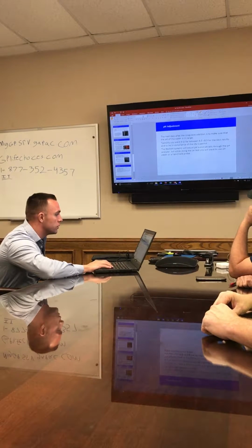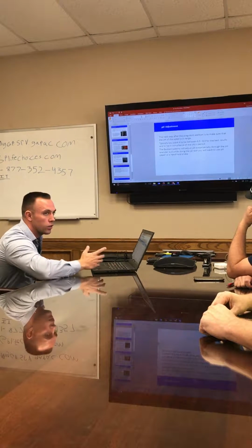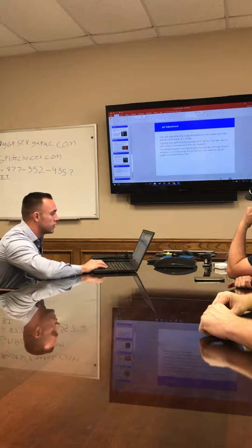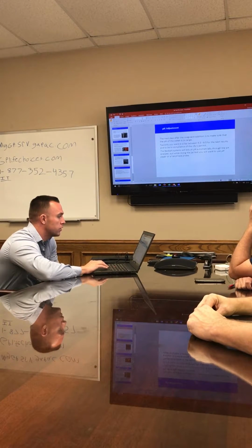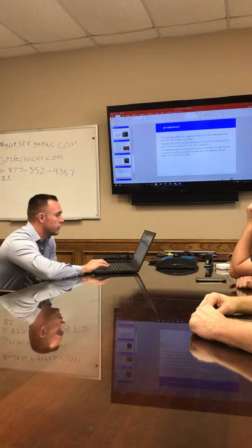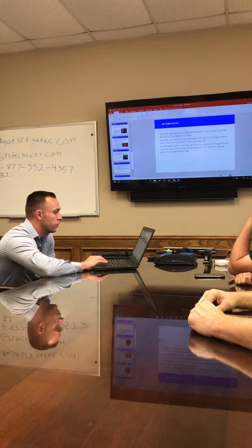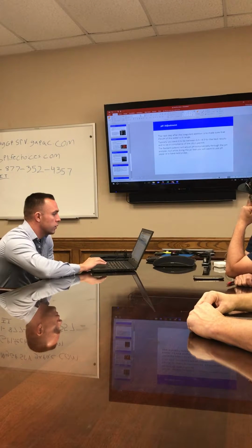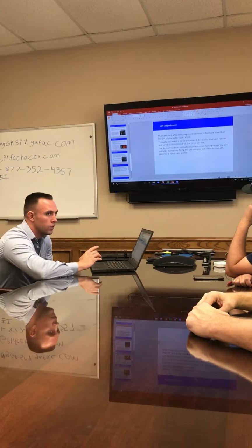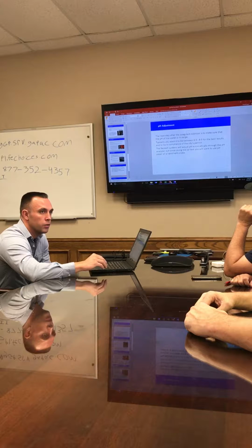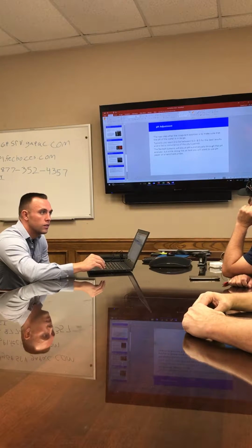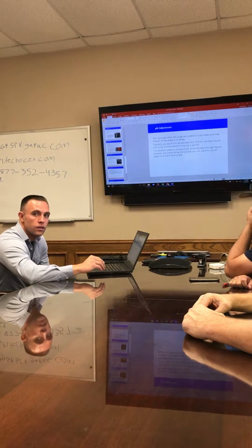Okay, pH adjustment. Now this is when you add your caustic. The next step after the coagulant addition is to make sure that the pH of the water is in range. Typically you want to be between 6.5 and 8.5 for the best results and to be in compliance with the city's permit. I think you guys are between 6 and 10, so you have a little bit more of a window than that, correct? Yeah, I believe so, right, Mark? Yeah. Okay.